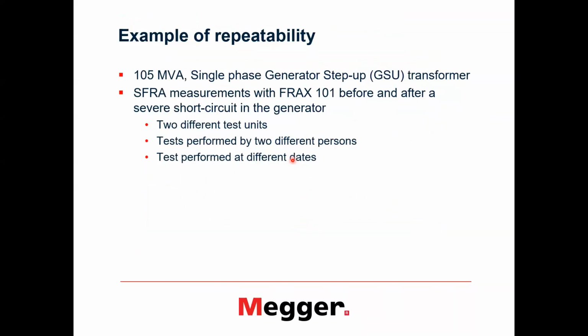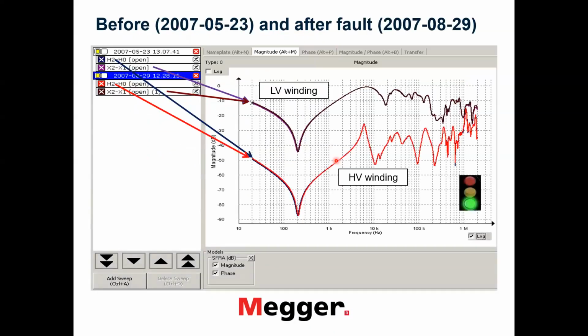Here is an example of how good repeatability could be if different test units were used, like different Fraxes, and different test persons performed a test at different dates after several short circuits in the generator. When we see the results from one day and the other day, we see perfectly lining up curves, which means that the testing personnel has done a good job. And what is even better, the best result here, is that the transformer looks fine. It was not damaged due to the short circuit in the generator.